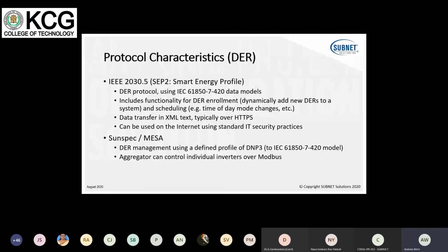The Smart Energy Profile is an IEEE standard that is for DERs. It maps onto those data models from 61850. It adds the enrollment functionality for adding new DERs and has scheduling functionality that is not a common thing in SCADA systems. So the scheduling might allow the DER to operate in different modes at different times of day. Based on standard IT practices, it transmits XML over HTTPS, so it can run over the internet.